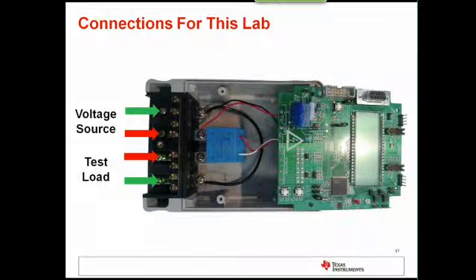You'll also see on here that we don't have those two separated anymore. Since we're actually connecting this to a line with a load, everything has to be in series. So whenever your mains comes in here, we're using this terminal on the EVM, it comes through the CT, so that's in series. It comes out through a test load on these two, then back in via this neutral wire to come back out.